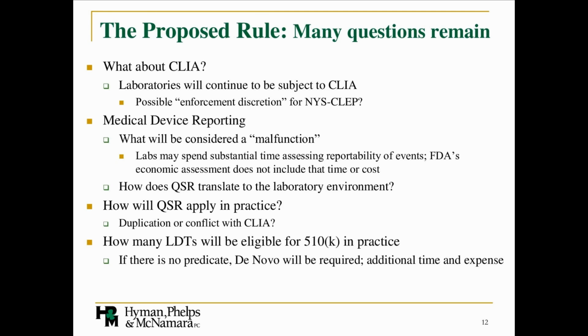Another big question is medical device reporting. So what does an adverse event look like in the context of a laboratory test? With devices, not only are reports required if a patient is actually injured, but reports are required if there is a quote unquote malfunction, which is defined in the regulations, that could have caused injury and could cause injury if it were to recur. So what is considered a malfunction in the context of a laboratory test? Anytime that there's a null result, whether or not it was reported out. So laboratories may spend substantial time having to assess whether events are reportable. And the FDA's economic assessment, which I'll talk about in a moment, doesn't include any consideration of the time or cost that compliance with MDR would require.